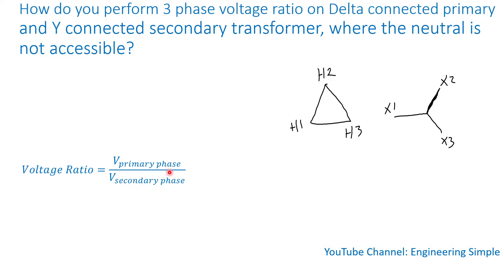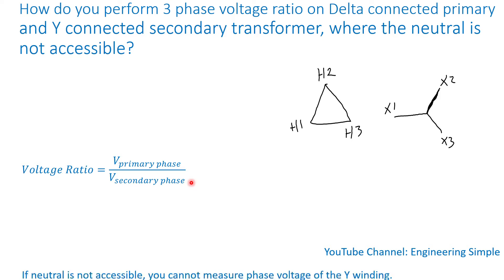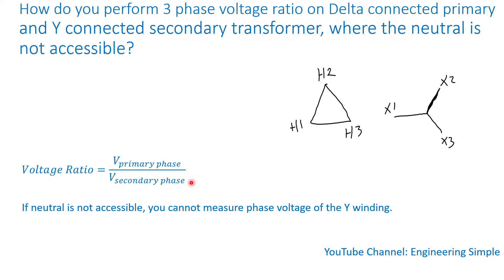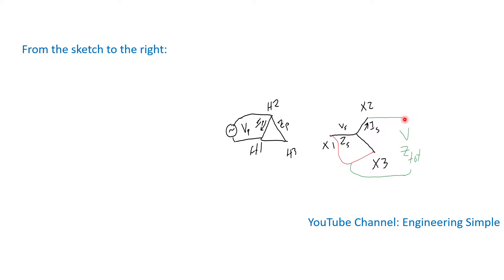The general formula for voltage ratio is the phase voltage of the primary side divided by the phase voltage of the secondary side. Because we have a delta and a Y: for the delta, the phase voltage is the same as line-to-line. For the Y, you have to use the phase voltage, or you can use line-to-line divided by square root of three — because if you don't, you'll be off by a factor of square root of three. Since the neutral is not accessible, you cannot measure the phase voltage of the Y winding.